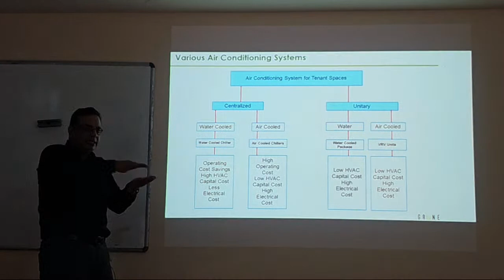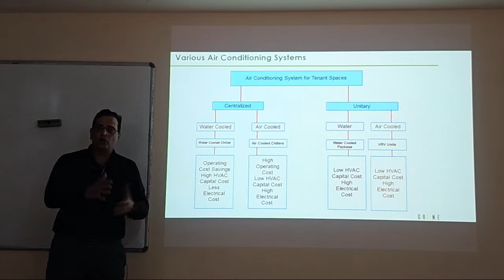Centralized system, we call it water-cooled. Water-cooled means you need a plant space. It needs to be put up in a building plan somewhere within the building. An air-cooled system is put outside the building on the terrace, and a unitary system is generally considered air-cooled splits or VRF units. They are unitary systems because they are not connected to the building. It is designed for a floor, or for an apartment, or for one common office. Central plant rooms are designed for a full building to work together, and that is where the highest energy savings come from, in terms of operations and cost. That should be the fundamental we are trying to look at in design.